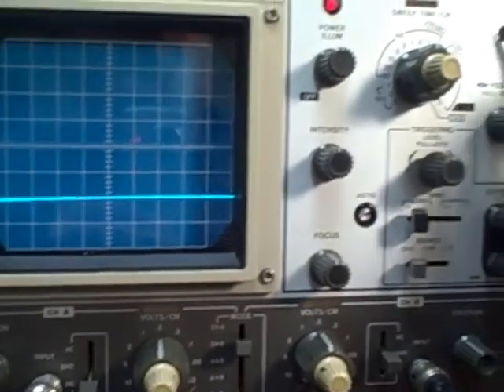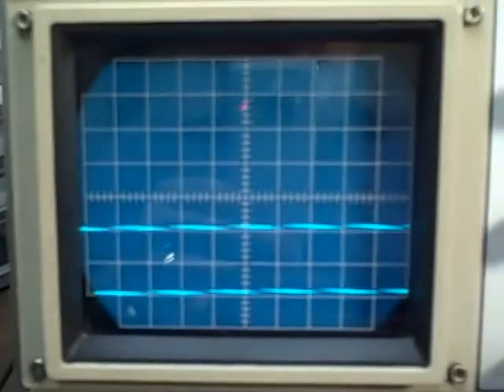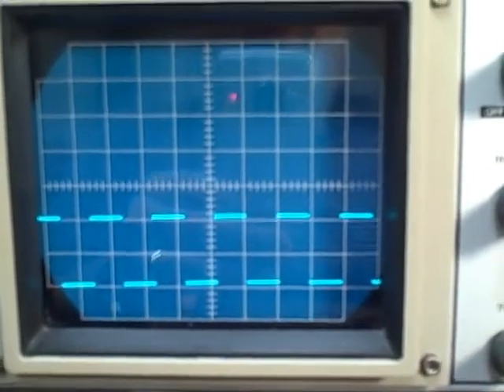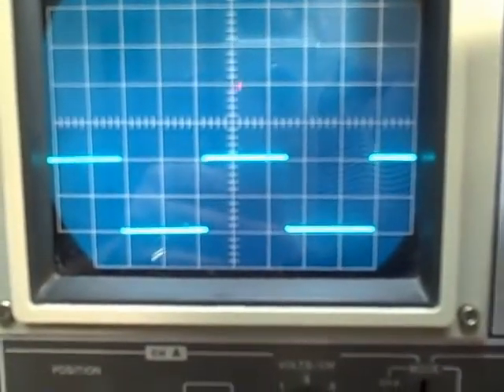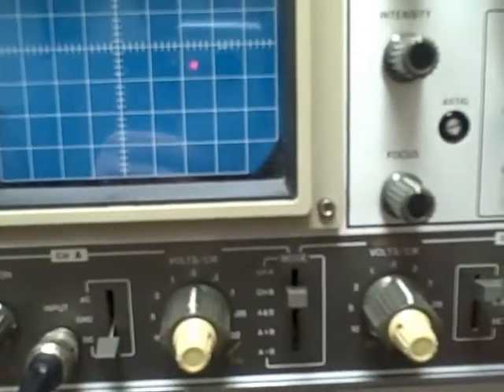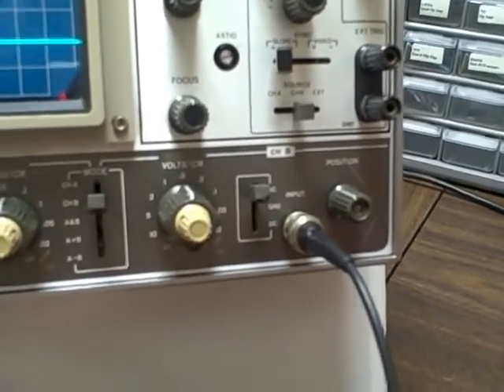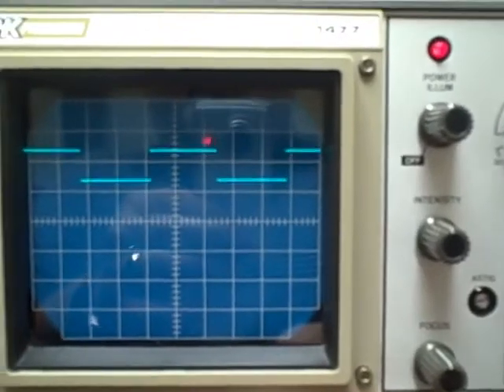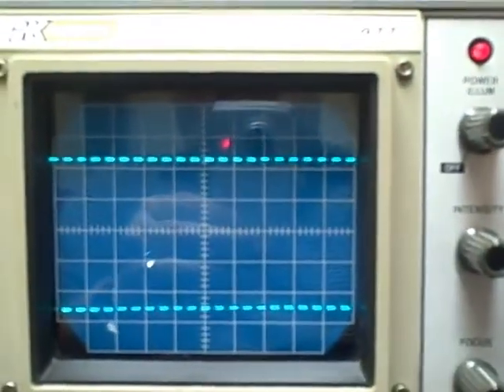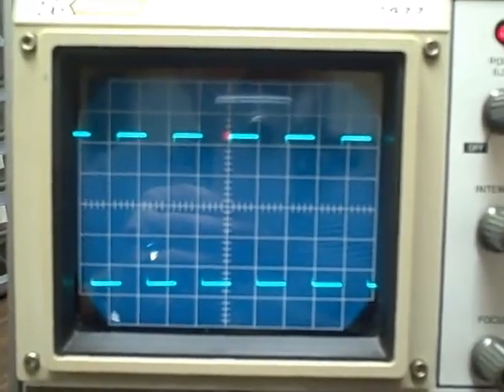Let's take a look at the calibration input. We'll go switch to channel 2 to show that. Alright, I just took myself up to the calibration point up here. And we'll go ahead and put ourselves on AC and our trigger source to channel B. And there you go. Not a problem. I could do the same with channel A. We'll try that right now. Give me a moment. Alright. And we'll go ahead and bring ourselves down again. There we go. Not a problem. Okay. Channel A and channel B are both working fine with the calibration point. Minor thing. Let's get on with the calibration checks, and we'll come back and finish up later.